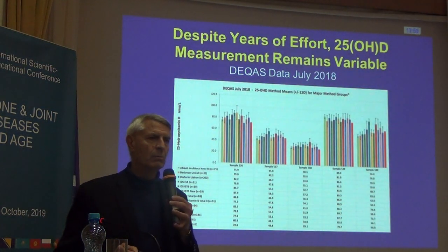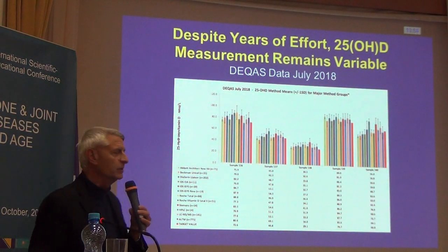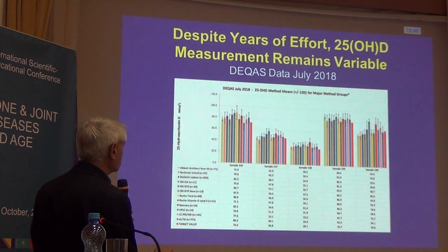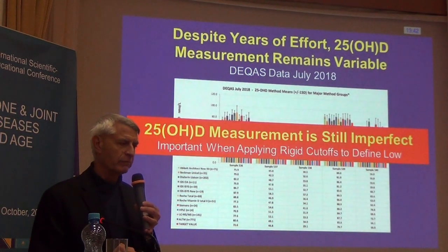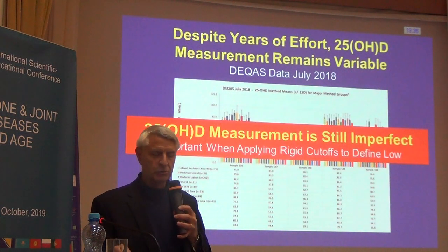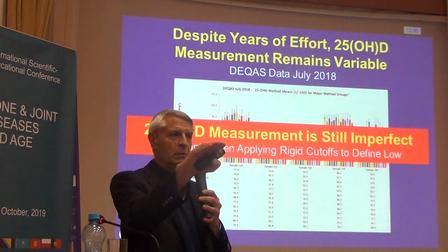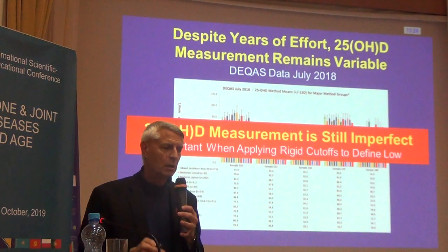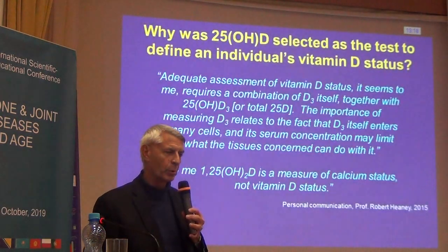Here are data from DEQAS — the Vitamin D External Quality Assessment Scheme — looking at averages across a number of assays on five sera. There is substantial variability in 25-hydroxy-D measurement. Despite years of trying, 25-hydroxy-D measurement is still imperfect. That's important when you're applying a rigid cut point of 20, 30, or 12 nanograms per milliliter — imperfect assays combined with rigid cut points create problems.